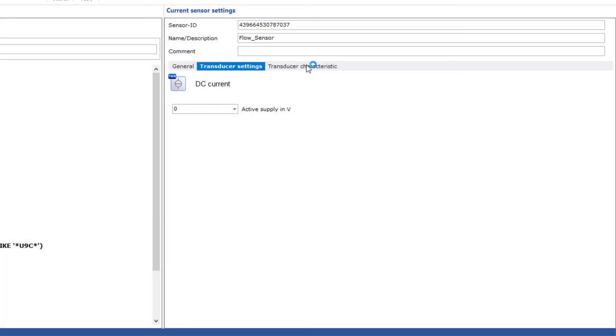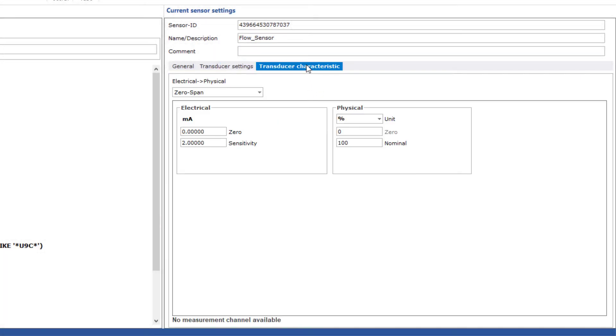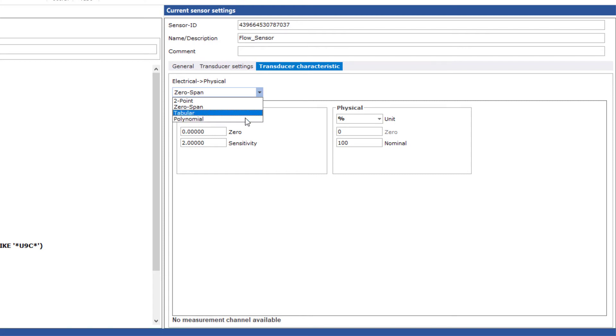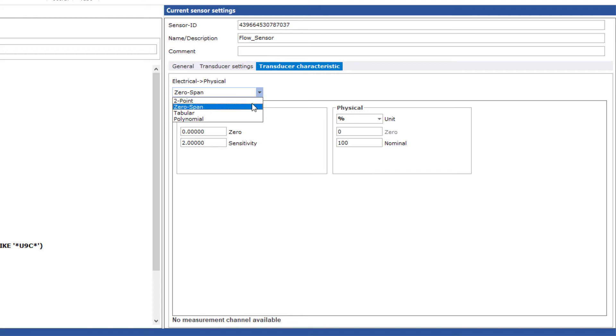Now switch to the transducer characteristic curve. Here you can use different methods to define the scaling. But when do you use which method? If you use a high precision sensor, the polynomial of the sensor is usually stored in the calibration protocol. Then use the polynomial. If you have a table with values in different levels in the calibration protocol, use the table. If the definition of the sensor's physical measuring range does not start with zero, use the two-point scaling. In all other cases, simply use the zero-point span method.